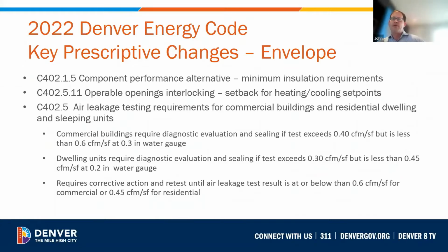The prescriptive envelope requirements have increased the required insulation for some assemblies. For example, there's a slight increase in continuous insulation requirements for steel frame walls and wood frame construction. Also, there is a new maximum U factor requirement, or minimum insulation equivalently, that applies to all compliance paths. This limits the trade-offs that can be used with a performance approach, and it also limits the trade-offs that can be done with ComCheck with a component performance alternative.